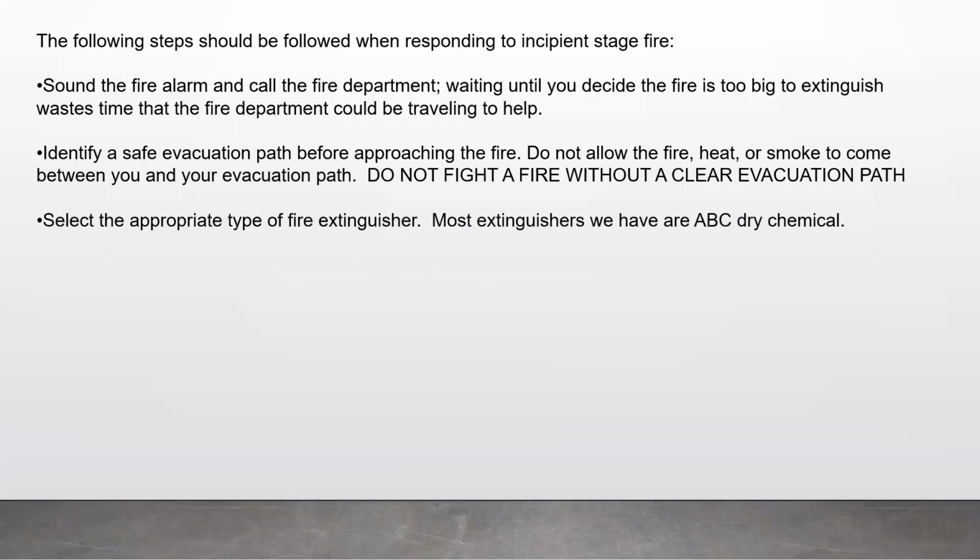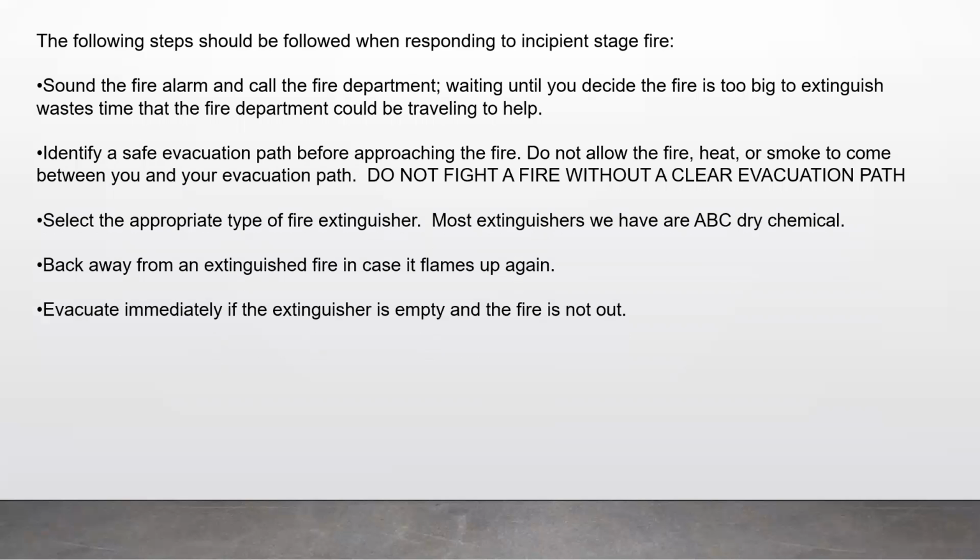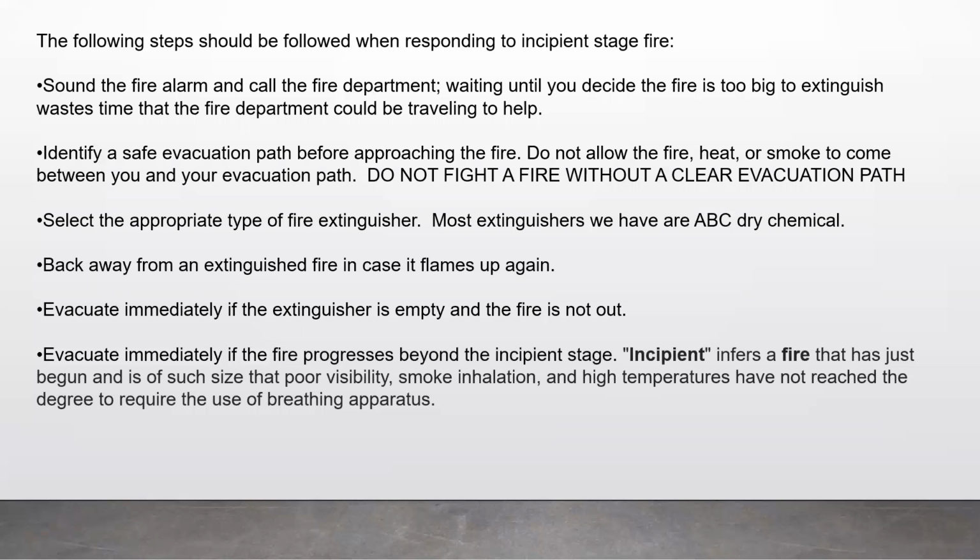Select the appropriate type of fire extinguisher. Most extinguishers we have are A, B, C dry chemical. Back away from the extinguished fire in case it flames up again. Evacuate immediately if the extinguisher is empty and the fire is not out. Evacuate immediately if the fire progresses beyond the incipient stage.